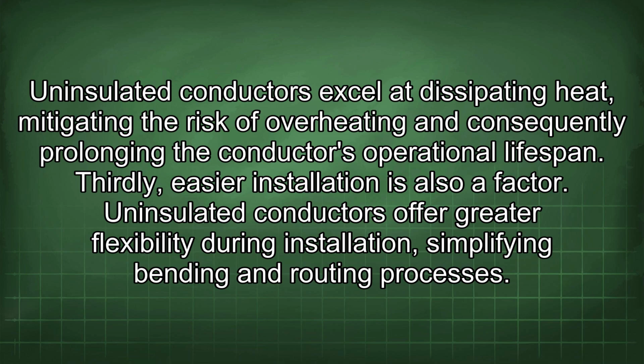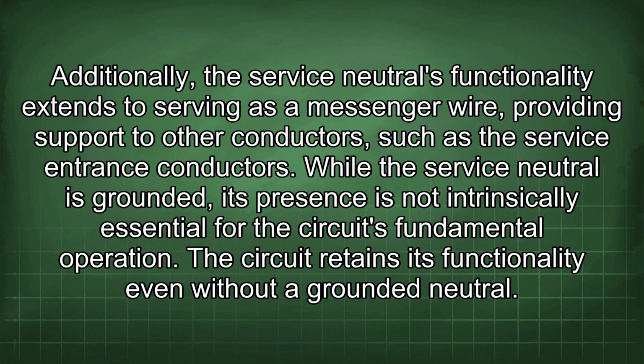Thirdly, easier installation is also a factor. Uninsulated conductors offer greater flexibility during installation, simplifying bending and routing processes. Additionally, the service-neutral functionality extends to serving as a messenger wire, providing support to other conductors such as the service entrance conductors. While the service-neutral is grounded, its presence is not intrinsically essential for the circuit's fundamental operation.